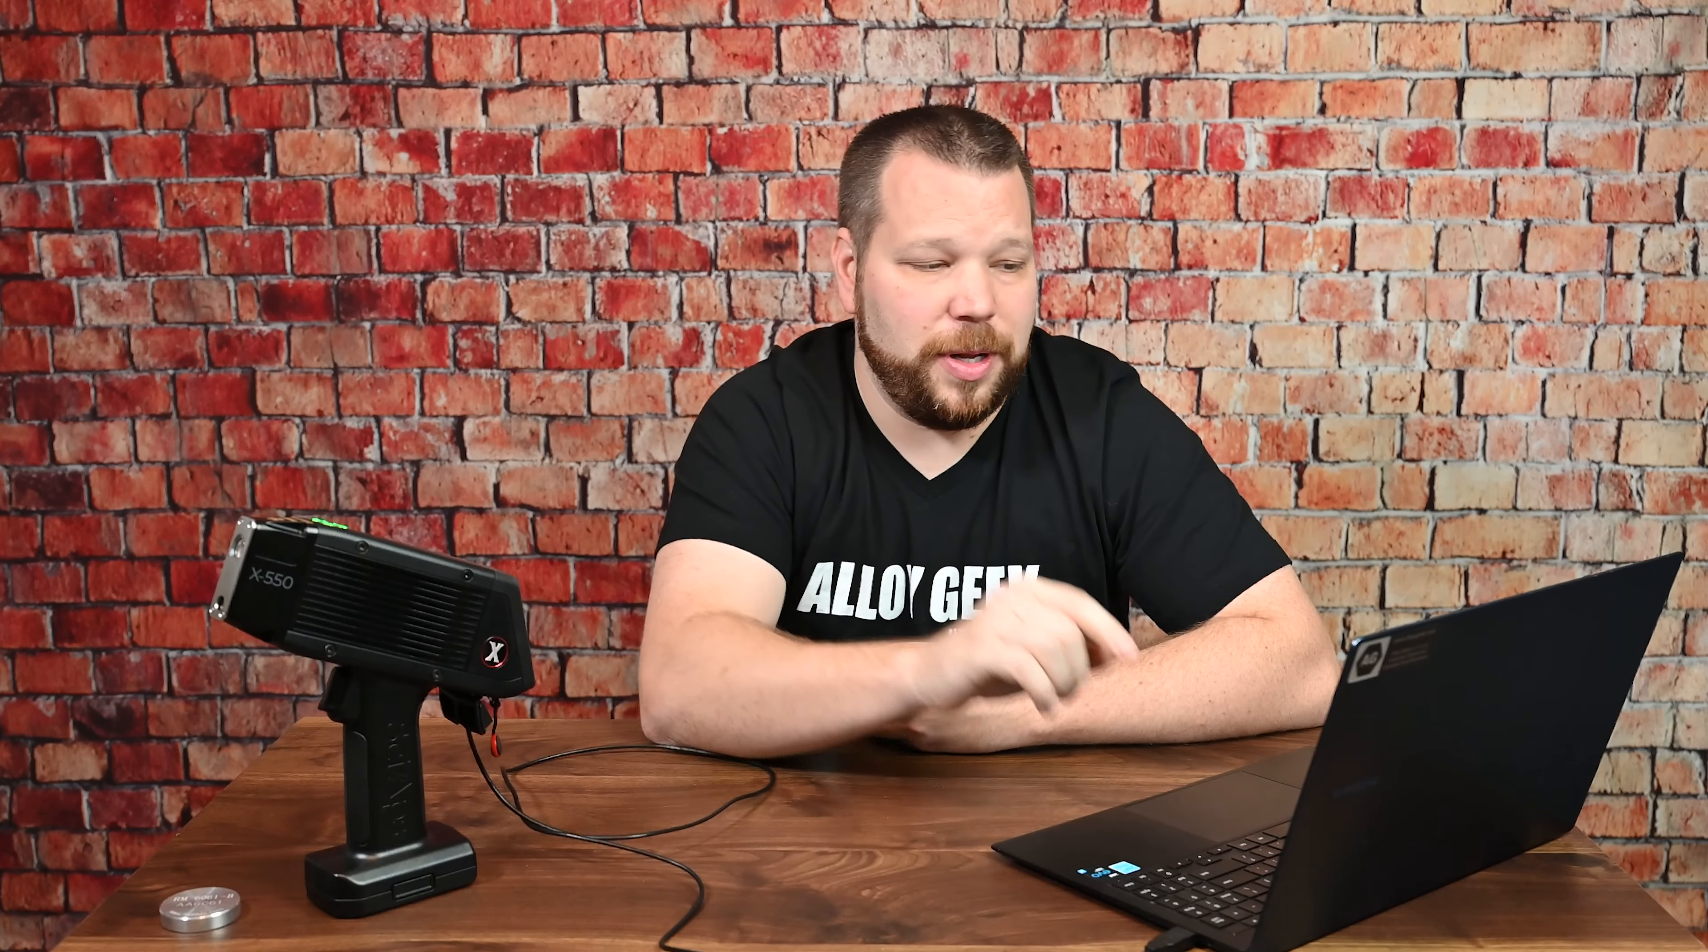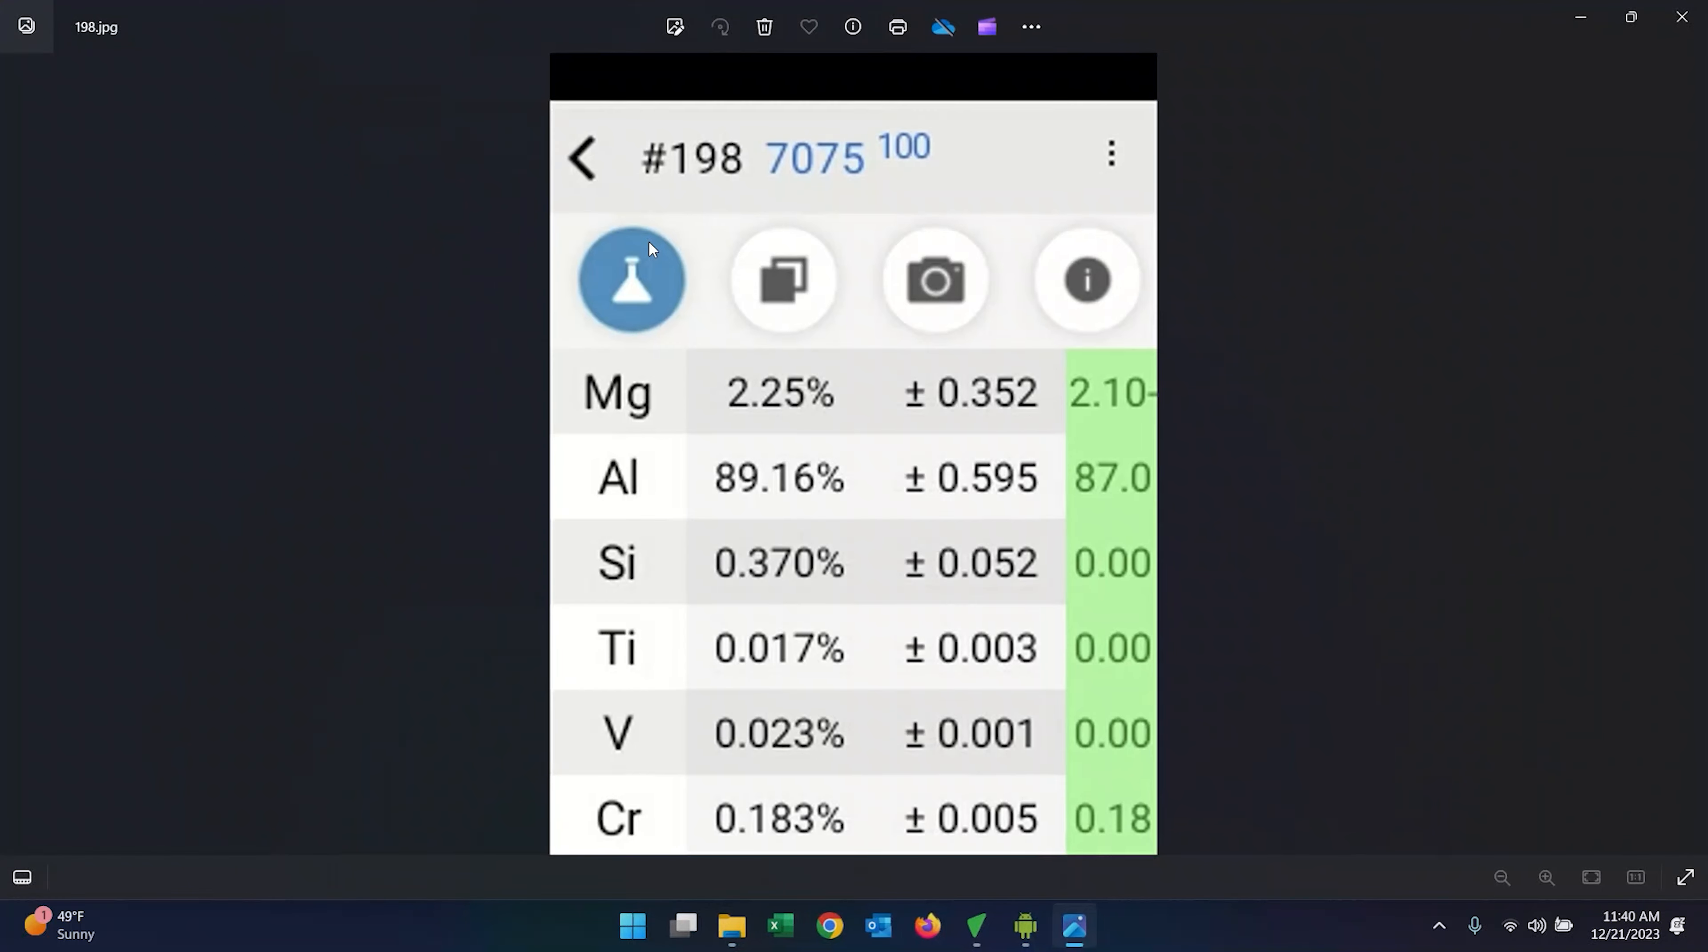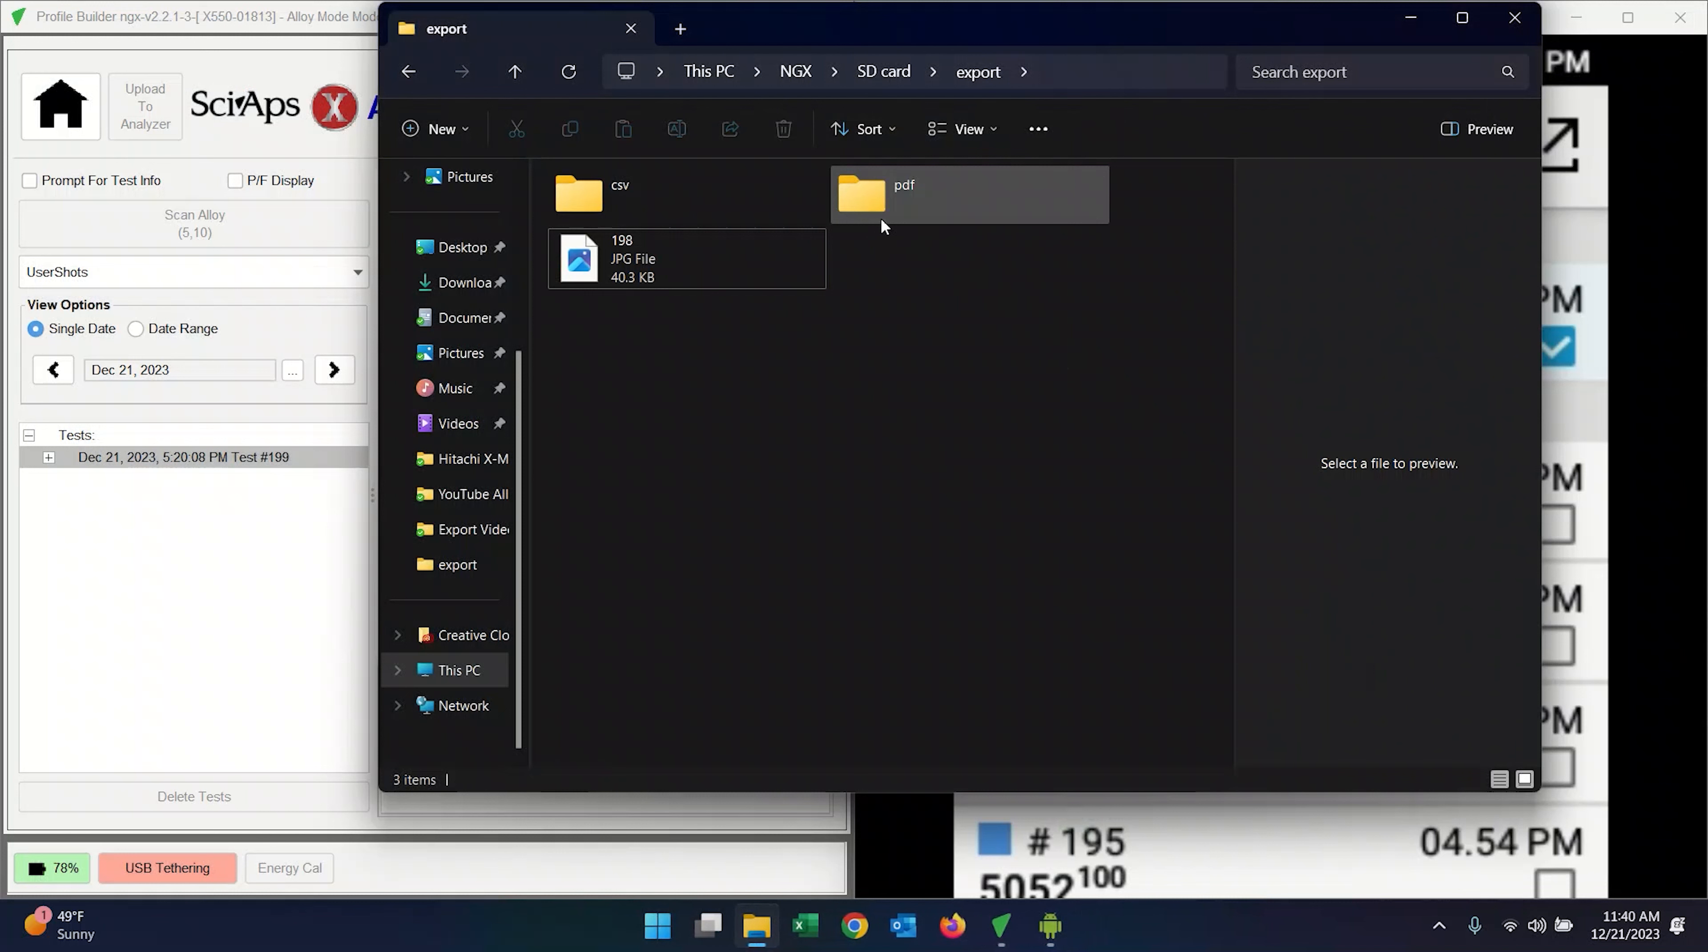Now I want to pause here for a moment and say there's essentially three ways to export different data from this device. The first way, I took a screenshot earlier and I really liked this. So if you were making a report for somebody or you wanted to show a result or show how the analyzer worked or create instructions for your organization, that's a great way to do that. You actually take screenshots in each result. You can do that and save them. They save right in this folder. I find that really helpful when I'm doing trainings and things.